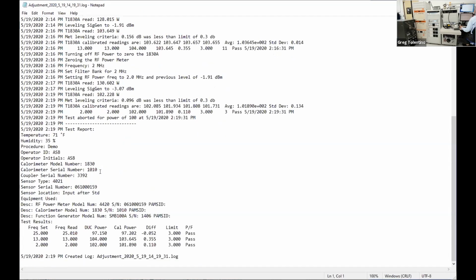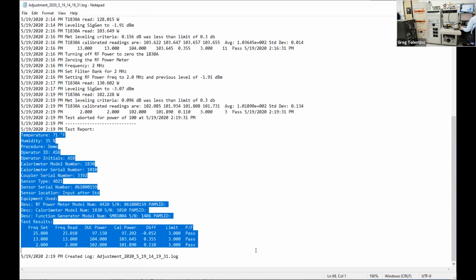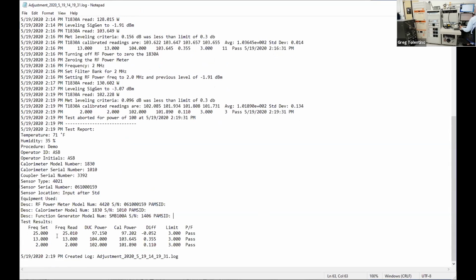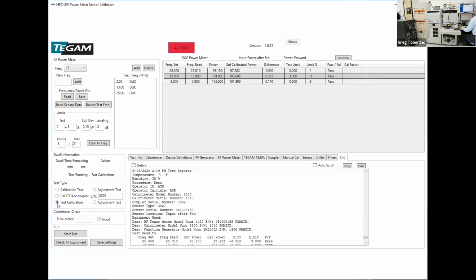All right, so there's all the record of the tests we did, and this part here is suitable for cutting and pasting into a report, with the frequencies. This part here, for these Bird sensors that have their own built-in frequency meter, is a good check of that. No provision is made for adjusting that because it's really just a counter, but you do want to check that it's reading right. So that's that. The sensor is now ready to go with its new calibration constants. And there's the report. In the event that you wanted to verify that the cal worked, you could come back to your application, switch it from an adjustment test to a fast calibration test, and it would just repeat that whole thing without burning the EEPROM. I'm not going to do that because it's so time consuming and it looks just like what you just saw. So let's not go there.